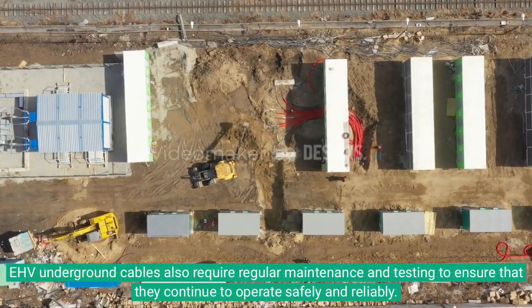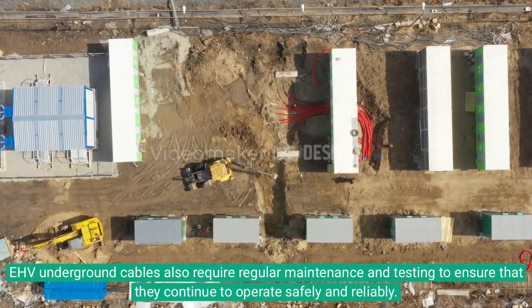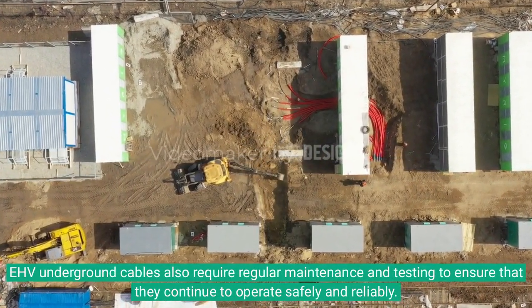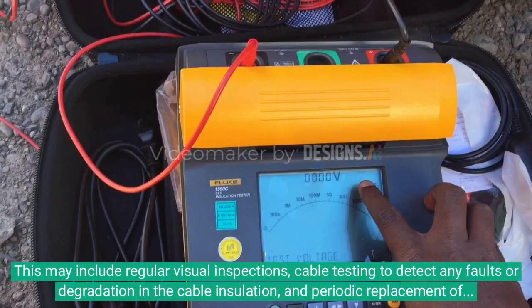EHV underground cables also require regular maintenance and testing to ensure that they continue to operate safely and reliably. This may include regular visual inspections, cable testing to detect any faults or degradation in the cable insulation, and periodic replacement of cable accessories such as terminations and joints.